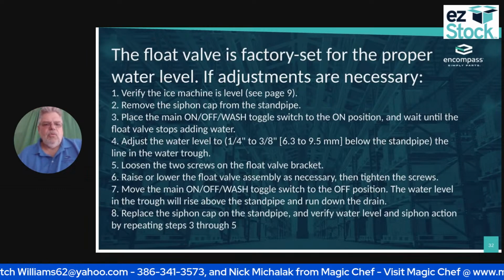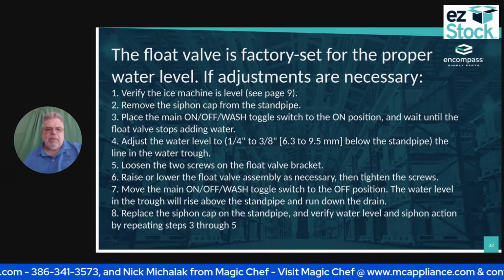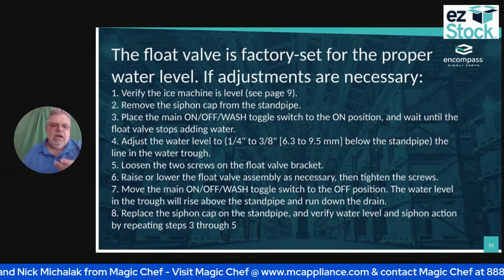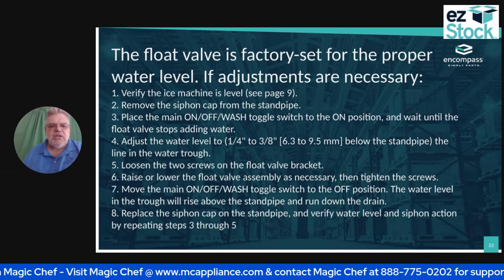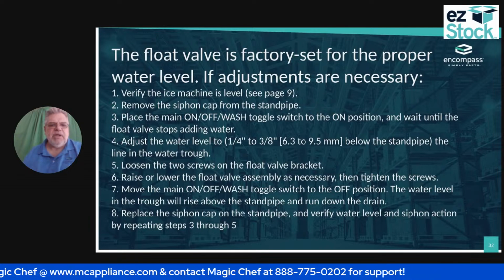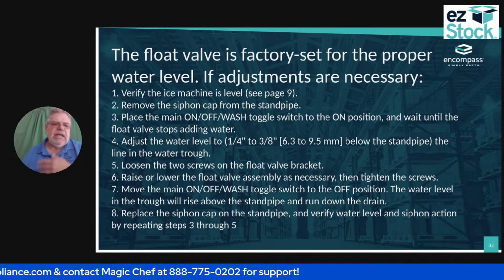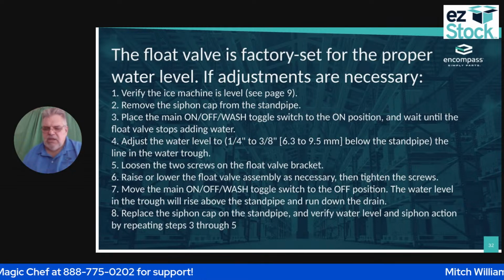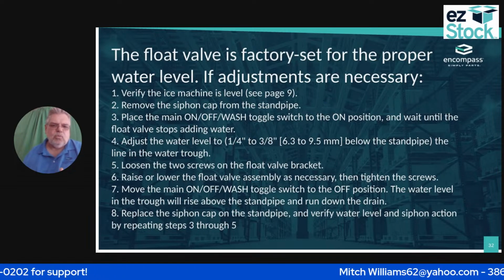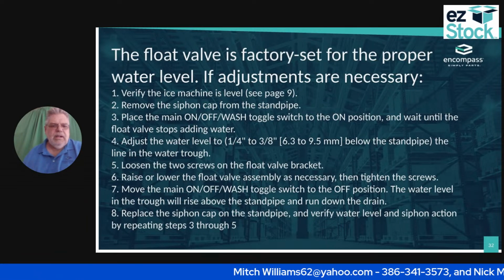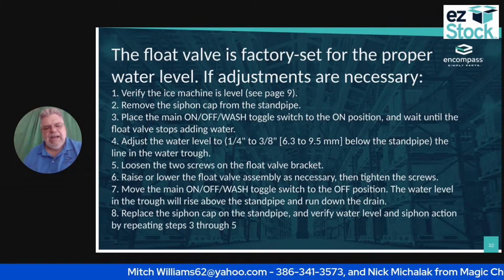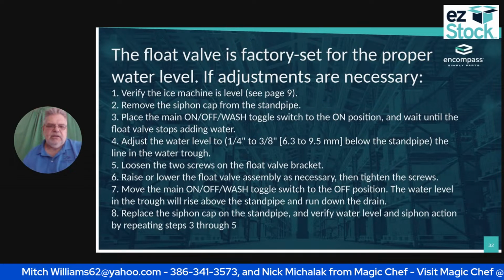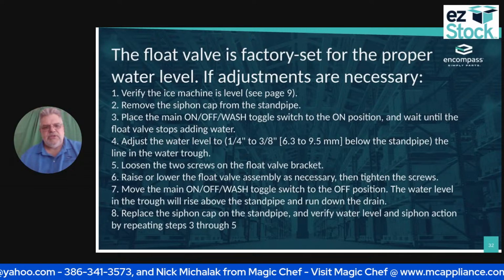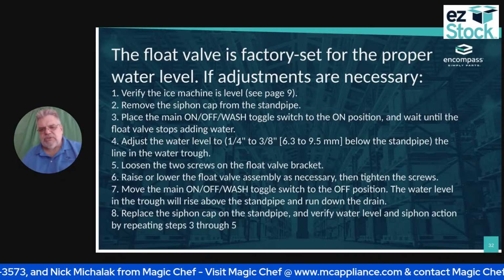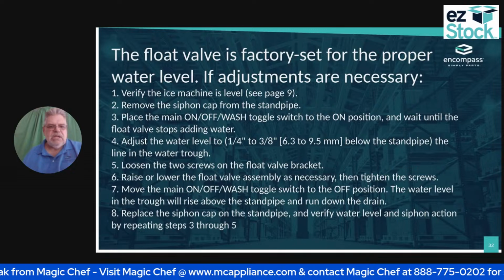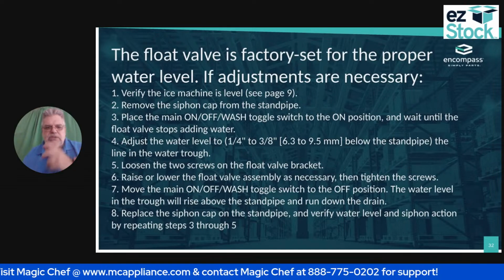Okay, so the float valve is factory set for the proper water level. If adjustments are made, you need to do this. If I'm going to make an adjustment, and I hate to tell you this, you need to at least watch it do 3 dumps just to make sure that it doesn't actually change. I have been out and I have found that somebody went and worked on it and adjusted the float valve and it was the wrong adjustment. So you need to let this go for at least 3 cycles.